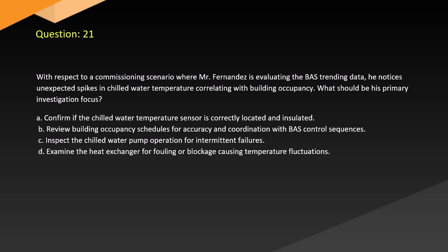Question 21. With respect to a commissioning scenario where Mr. Fernandez is evaluating the BAS trending data, he notices unexpected spikes in chilled water temperature correlating with building occupancy. What should be his primary investigation focus? A. Confirm if the chilled water temperature sensor is correctly located and insulated. B. Review building occupancy schedules for accuracy and coordination with BAS control sequences. C. Inspect the chilled water pump operation for intermittent failures. D. Examine the heat exchanger for fouling or blockage causing temperature fluctuations.